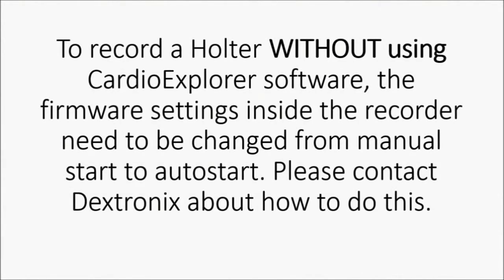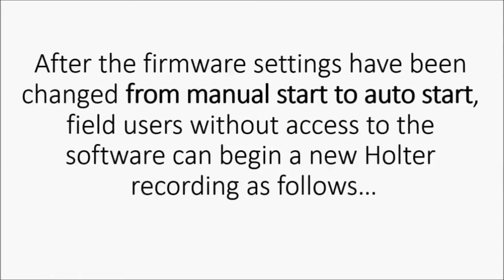To record a Holter without using Cardio Explorer software, the firmware settings inside the recorder must be changed from Manual Start to Auto Start. Please contact Dextronix and we will assist you. After the firmware settings have been changed from Manual Start to Auto Start, field users without access to the software can begin a new Holter.